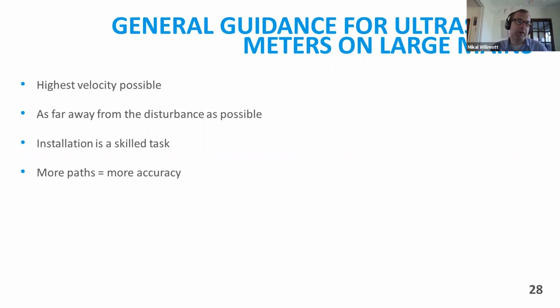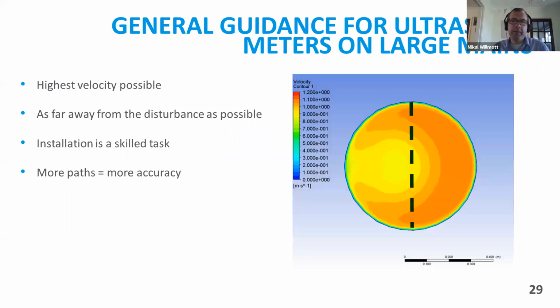And the other thing I'd like to add is that more paths lead to more accuracy. So here's a flow profile. You'll see that there's a higher flow rate, higher velocity on the right-hand side. We put one ultrasonic path, and we're probably going to get an under recording here because we missed the high flow rates. Now we put 2 paths on, we get a better picture. And if you want to hit the button again, Andy, we put a few more paths on, and there we get a better picture on that.